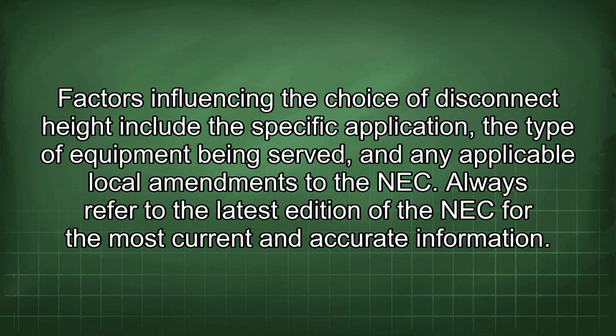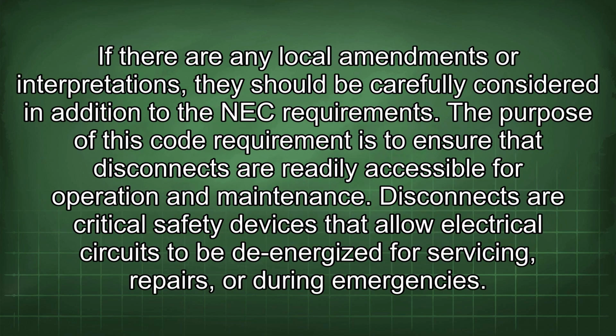Factors influencing the choice of disconnect height include the specific application, the type of equipment being served, and any applicable local amendments to the NEC. Always refer to the latest edition of the NEC for the most current and accurate information. If there are any local amendments or interpretations, they should be carefully considered in addition to the NEC requirements. The purpose of this code requirement is to ensure that disconnects are readily accessible for operation and maintenance.